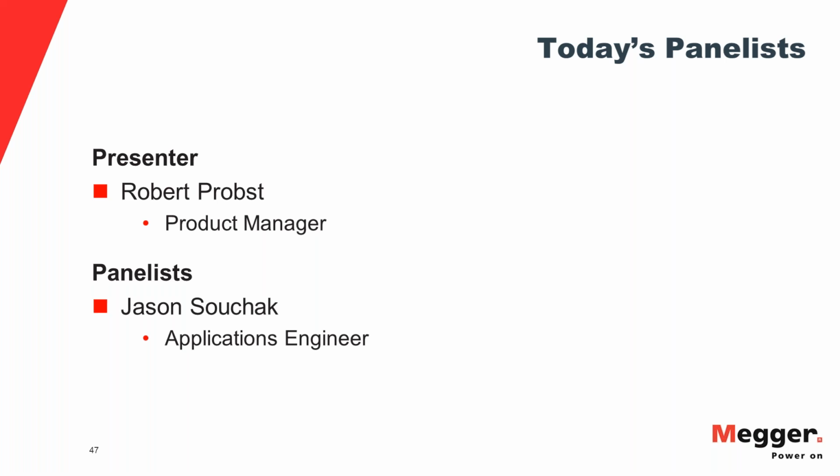And now on the acceptance test, initially, in the IEC world, it was 60 minutes as well. And in the main standard, it still is. However, there's a second IEC standard that is specifically mentioning the acceptance test. And for the acceptance test, they also require, again, 3 times U0 RMS for 15 minutes. And the reason for that is the industry learns.